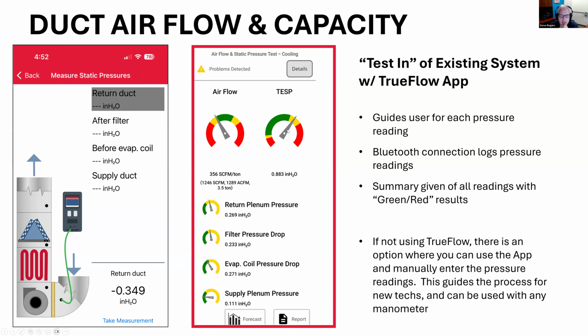But what's important is we take that static pressure, TESP, and we break it down into the four components. So if you add these four subdials, we call them, they add up to 0.883. And these are important because they can point you to where you should work on improving the duct system, if you're not capable of getting the airflow that you need for the correctly sized system. If I were to look at this system here, we'll start at the bottom. Supply plenum pressure tells me, are the supply ducts properly sized? That's right in the middle of the green.